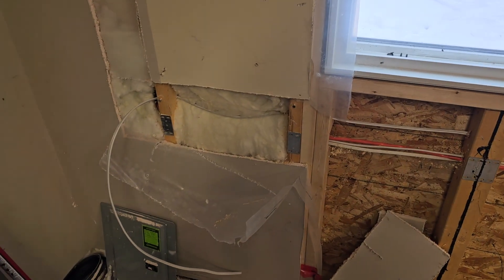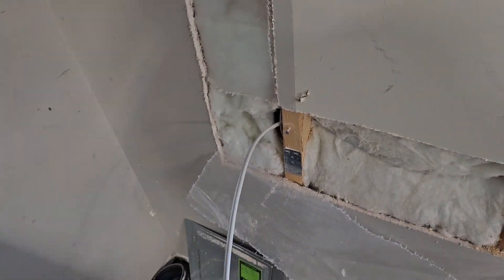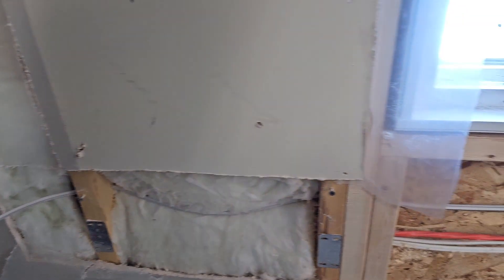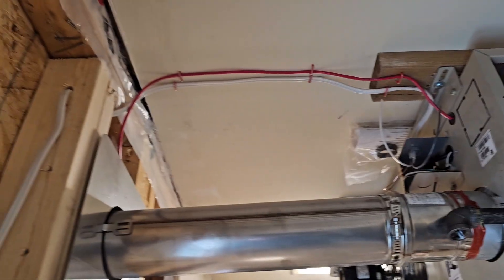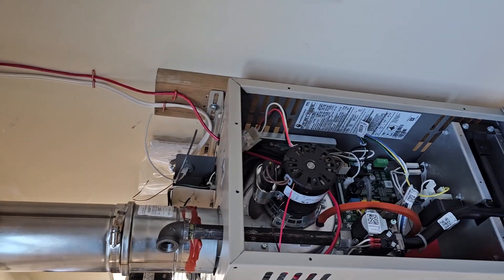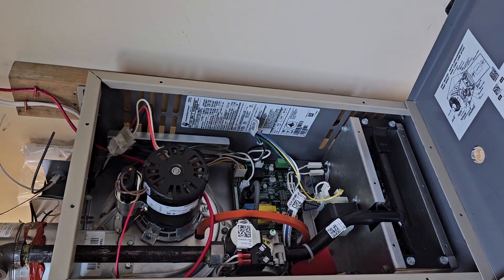I've already pulled my wiring here just to get things moving quicker. I have my 14/2 NMD cable that's going to go to this panel right here — I just basically pulled it along the wall. This upper one went up, and my red thermostat cable, it's just an 18/2 basic, brings it into the back of the heater and connects to the thermostat connections on the circuit board.